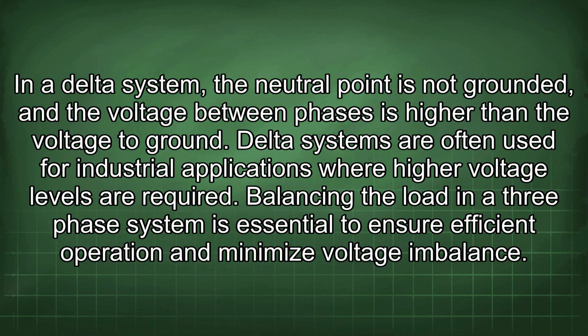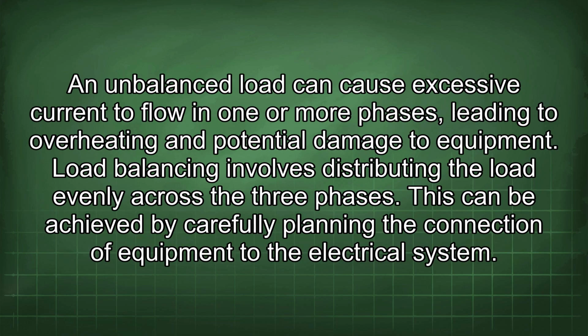Balancing the load in a three-phase system is essential to ensure efficient operation and minimize voltage imbalance. An unbalanced load can cause excessive current to flow in one or more phases, leading to overheating and potential damage to equipment. Load balancing involves distributing the load evenly across the three phases. This can be achieved by carefully planning the connection of equipment to the electrical system.